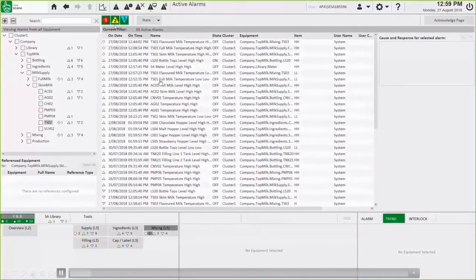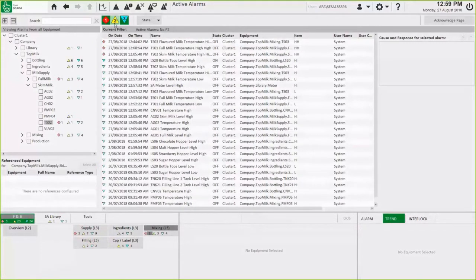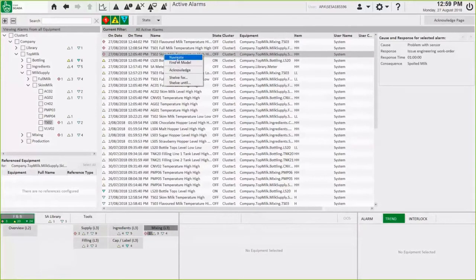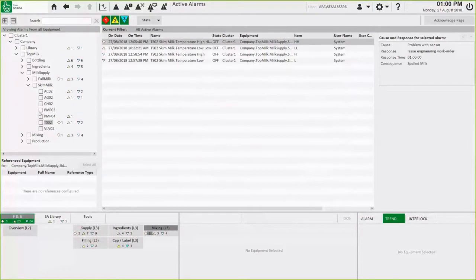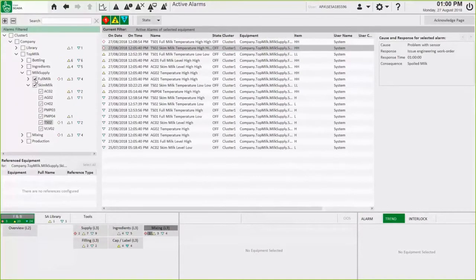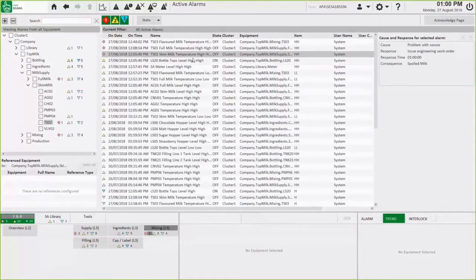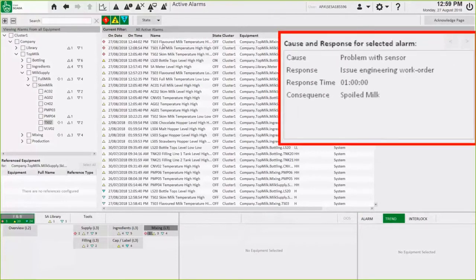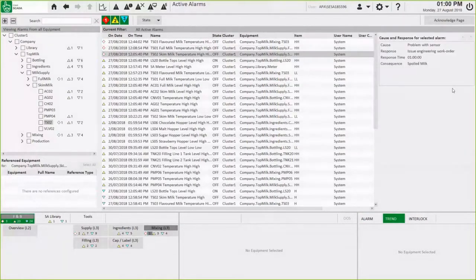Here I have a list of all the alarms which I can filter on priorities one, two, or three. I can also find any alarm in my plant model and filter out on either pieces of equipment or areas to get a clearer picture of the alarms that are happening. I'm also able to look at any causes and responses relevant to a specific alarm so the operator can take further action, and from the alarm page I can navigate back to my mimic.